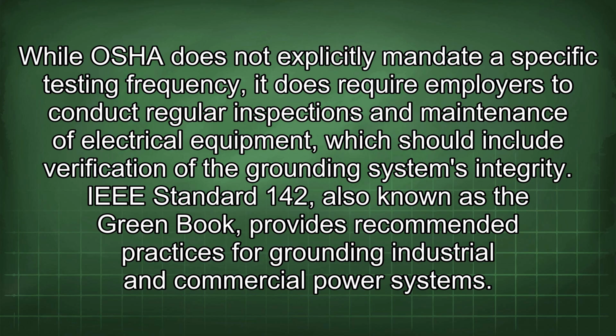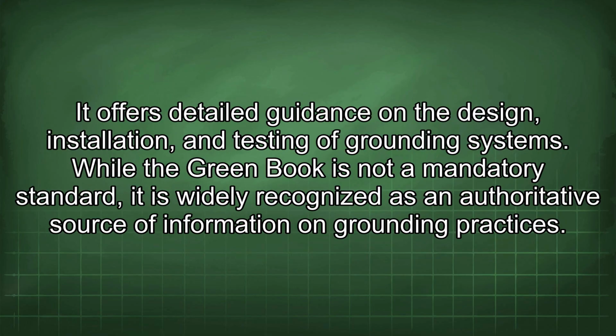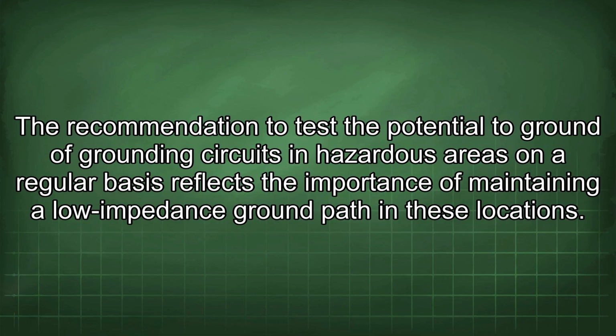IEEE Standard 142, also known as the Green Book, provides recommended practices for grounding industrial and commercial power systems. It offers detailed guidance on the design, installation, and testing of grounding systems. While the Green Book is not a mandatory standard, it is widely recognized as an authoritative source of information on grounding practices. The recommendation to test the potential to ground of grounding circuits in hazardous areas on a regular basis reflects the importance of maintaining a low impedance ground path in these locations.